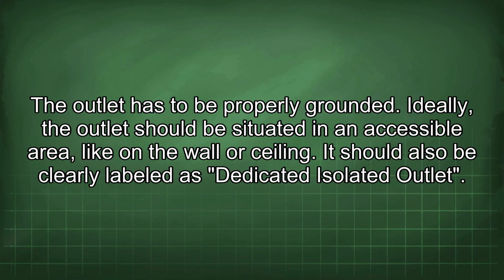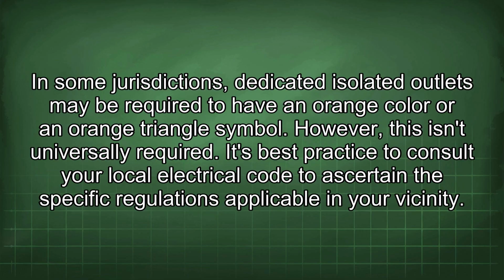Ideally, the outlet should be situated in an accessible area, like on the wall or ceiling. It should also be clearly labeled as dedicated isolated outlet. In some jurisdictions, dedicated isolated outlets may be required to have an orange color or an orange triangle symbol. However, this isn't universally required. It's best practice to consult your local electrical code to ascertain the specific regulations applicable in your vicinity.